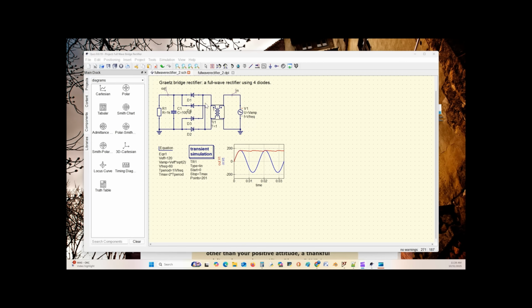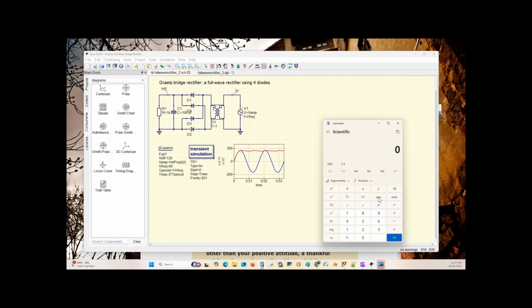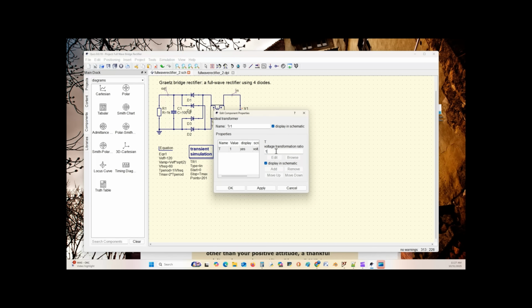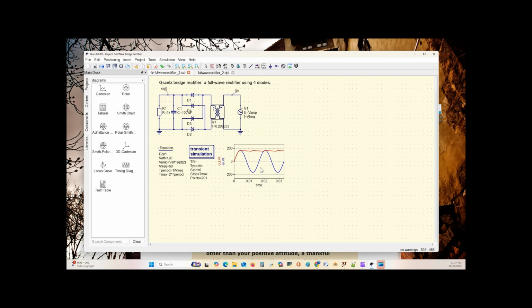Concerning this transformer being a 1-to-1, we're getting 120 volts in and 120 volts out. We don't want that, we want 120 volts in and 25 volts out. So we take our calculator: 120 divided by 25 makes 4.8, and that divided into 1 gives me 0.208333, repeating, so just do it a couple times. I come over here and convert the 1 to 1 to 0.208333. Hit apply, say OK, come up.